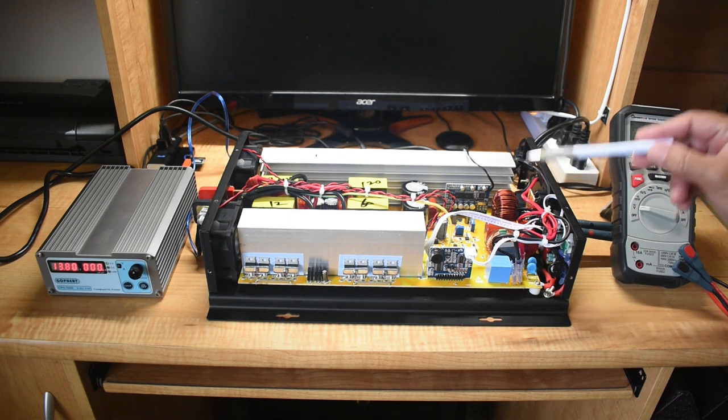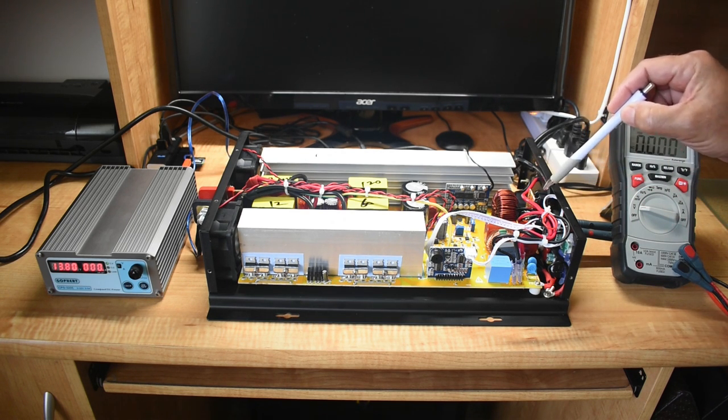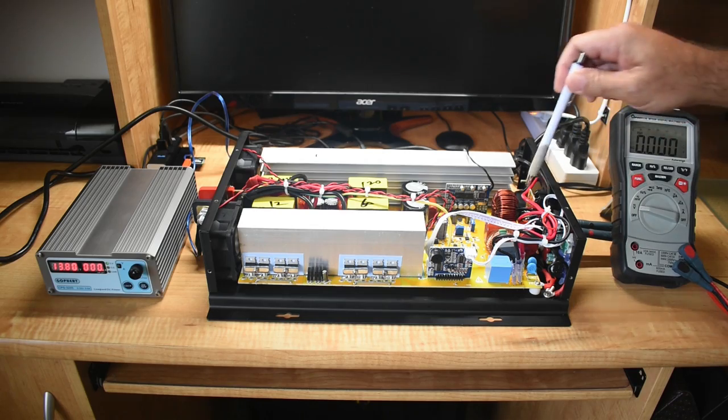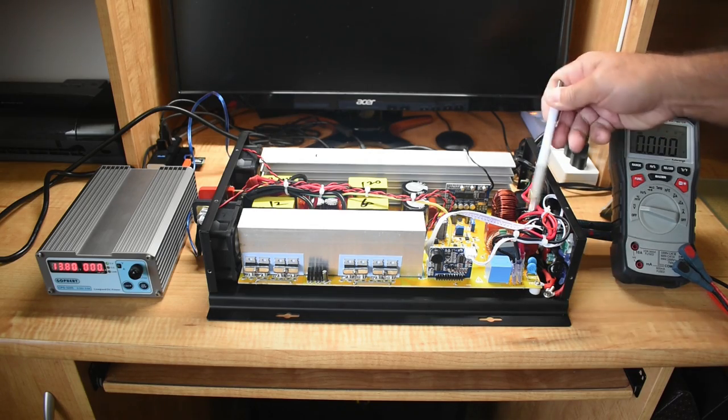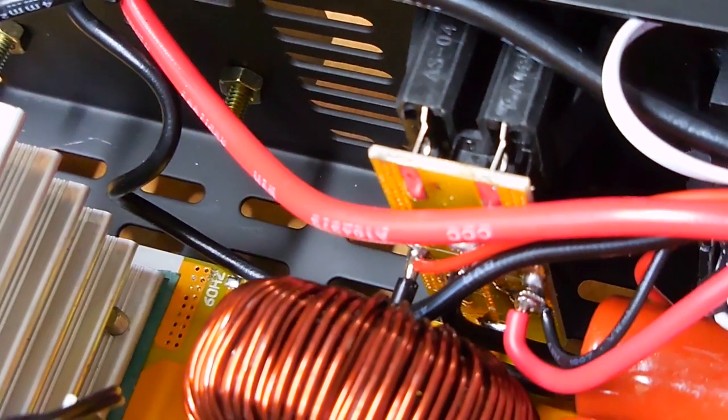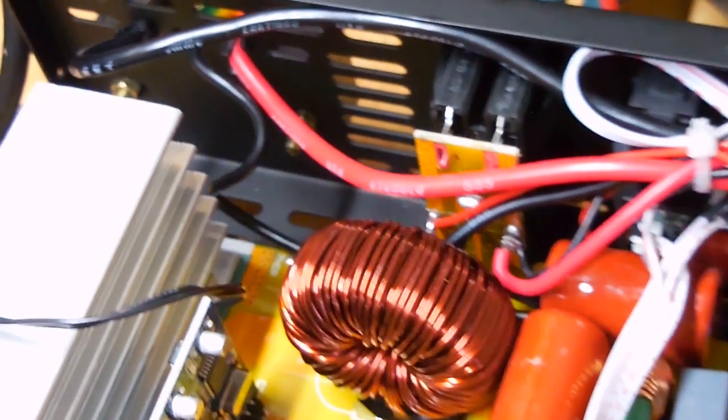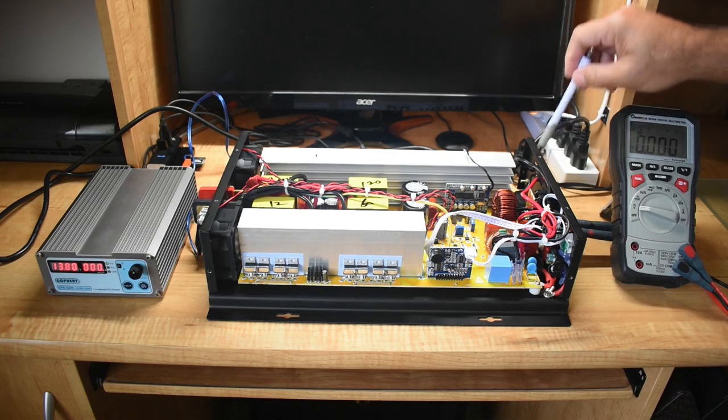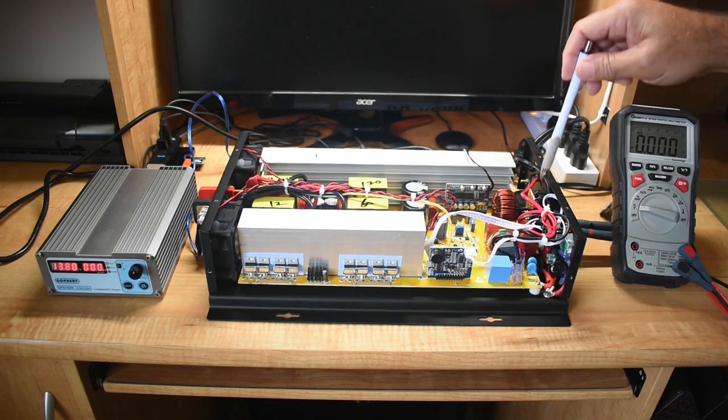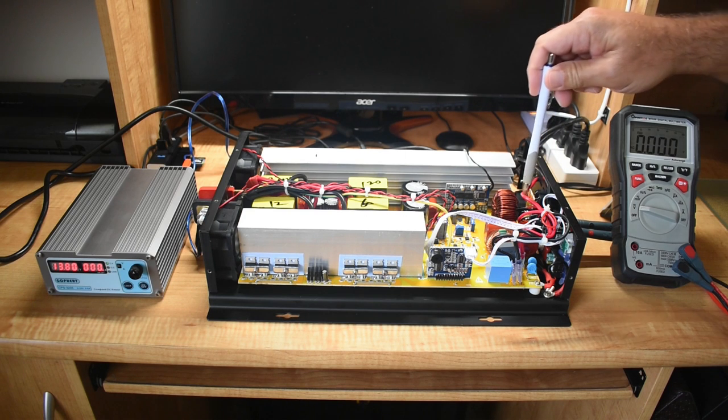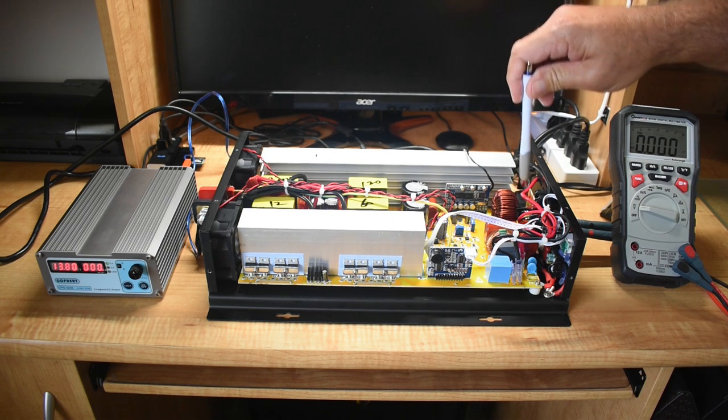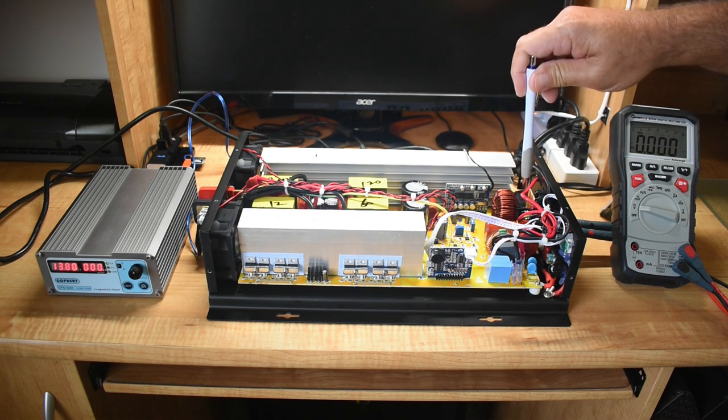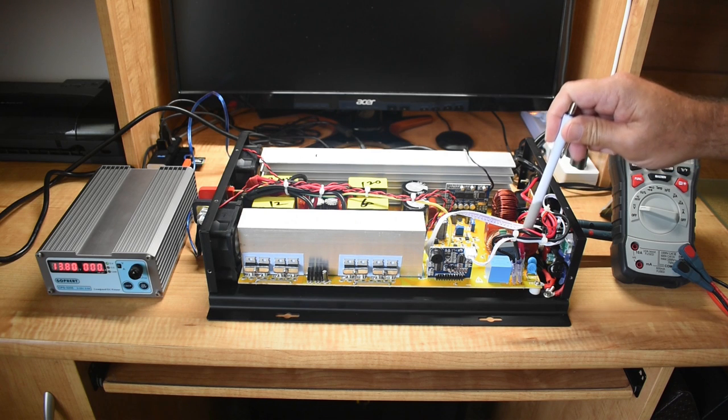When I opened up the unit later, you could see that the wiring going to the receptacles is this red wire right here. It's smaller than this thicker red wire going to the terminal block. And it doesn't make sense to me, because there's no reason why they couldn't have used a heavier wire between here and the board.